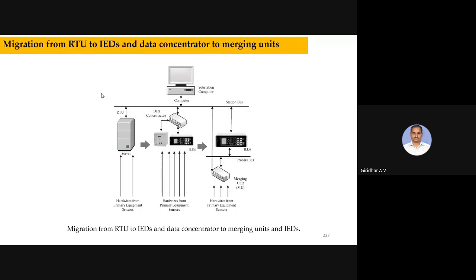So you can see there is a migration from RTUs to IEDs, then again to data concentrators, and again to merging units. There are different changes with respect to speed, with particular protocols and all. These changes were made. Typically, with sensors and field devices, RTUs were going, so from there to IEDs, and again data concentrators connected directly to the substations, like that they have used.